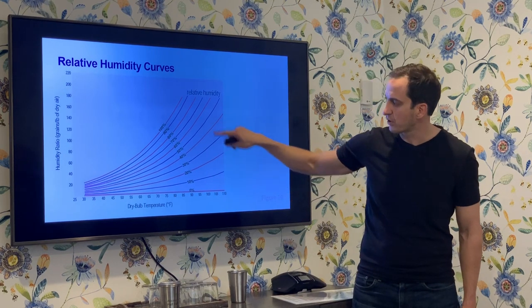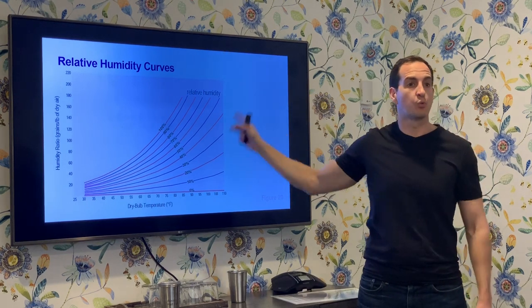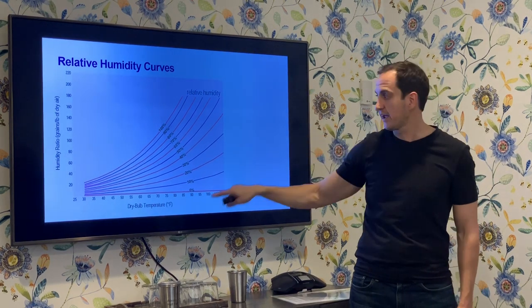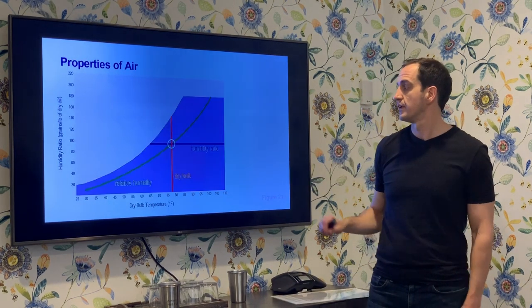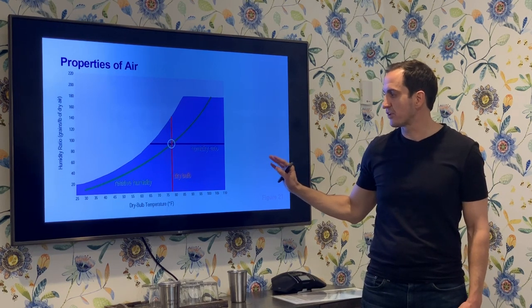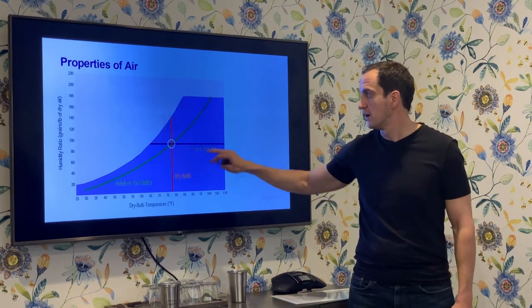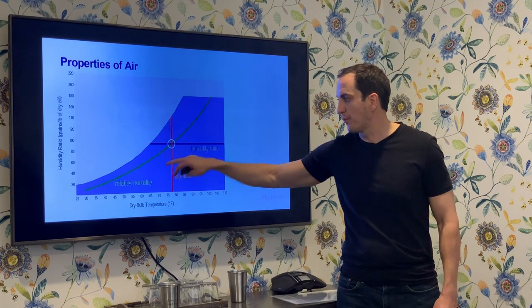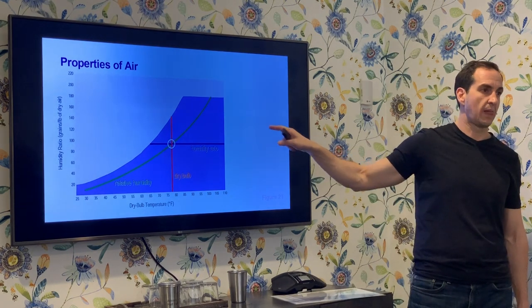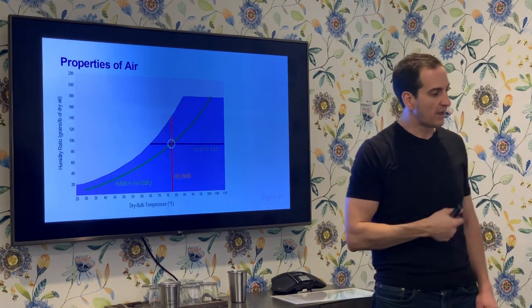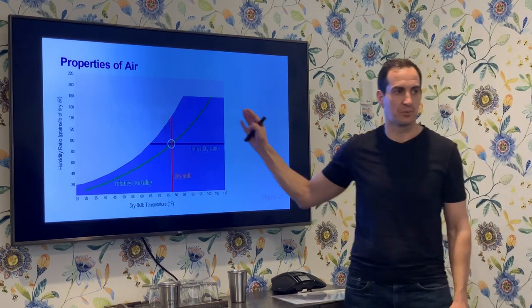These relative humidity curves indicate in an exponential way how much water the air could hold at saturation, and how much more it could hold at any condition. The humidity ratio, dew point, dry bulb, and relative humidity all match up: you can use any one of these points to find your way around the chart. You really need two out of the seven or eight different ways we measure air properties to find our place on the chart.